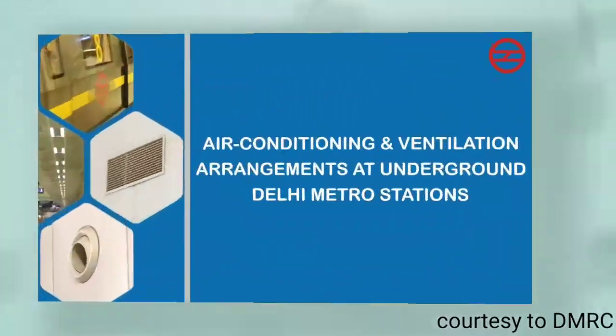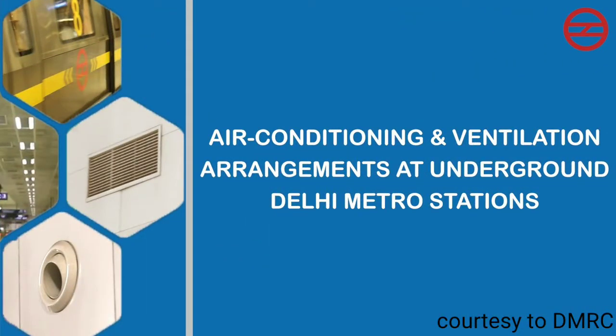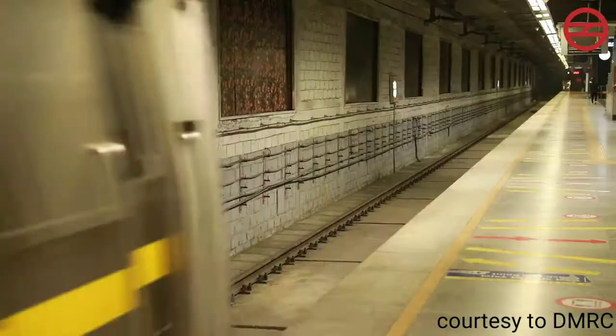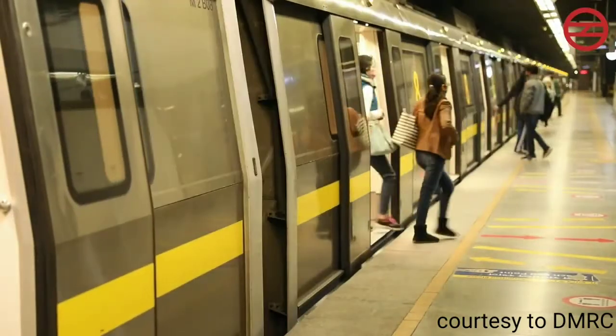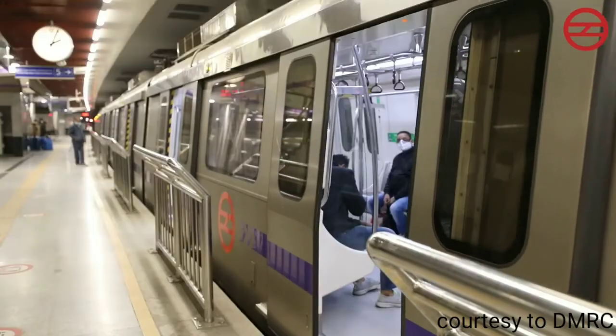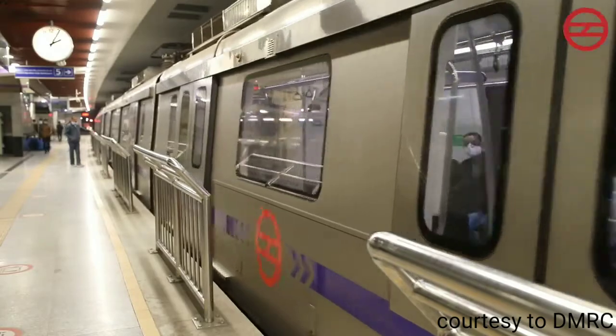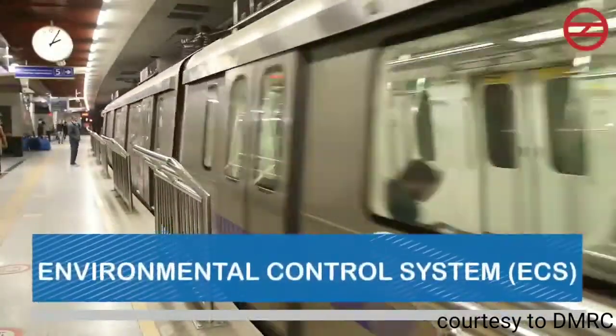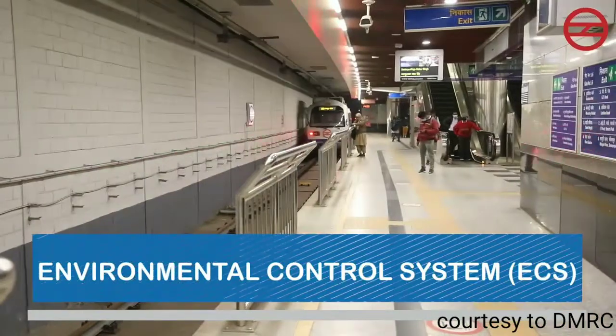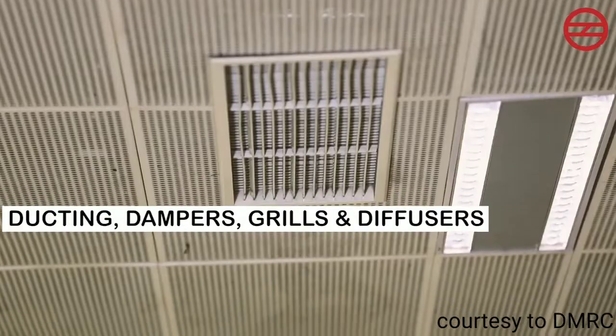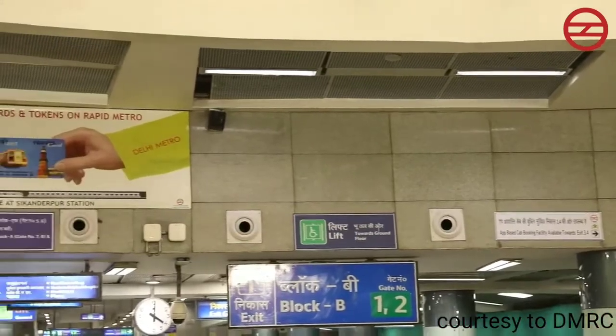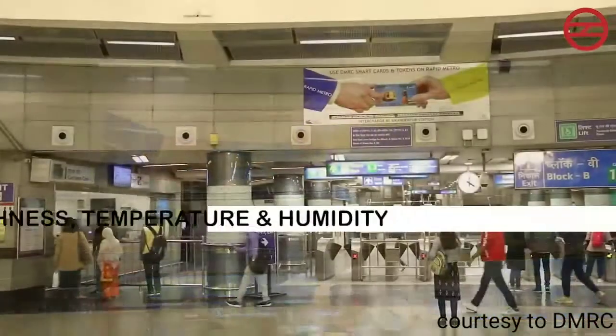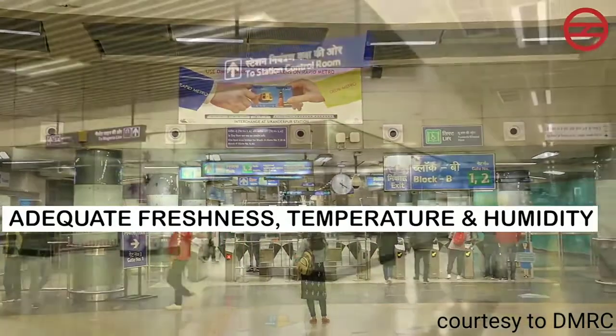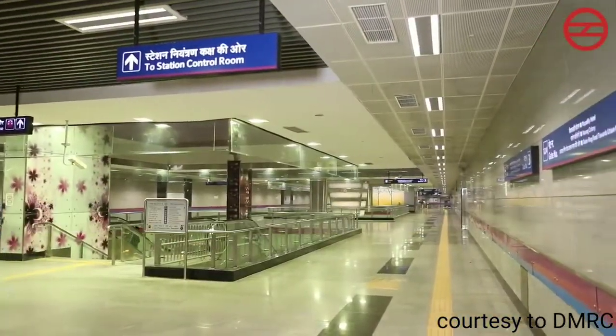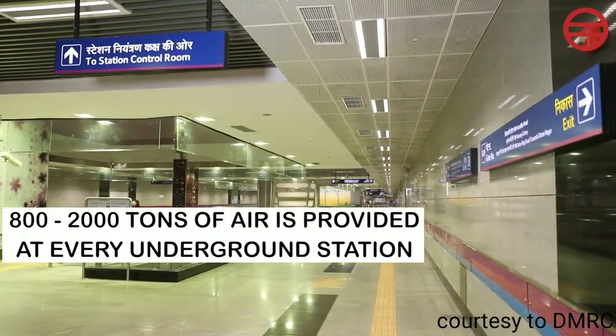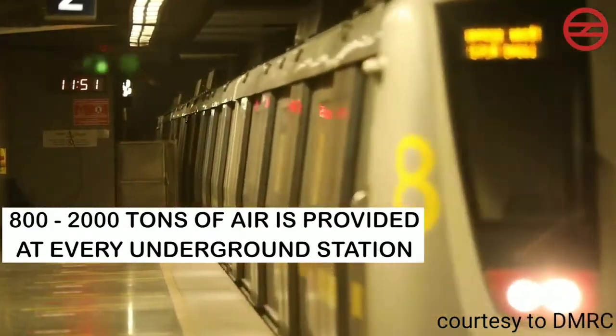Air conditioning and ventilation arrangements at underground Delhi metro stations. For supply of fresh air and removal of body heat, as well as heat generated from electrical equipments in train, a system of air conditioning and ventilation underground is provided, known as Environmental Control System, that is ECS. The ducting, dampers, grills and diffusers, etc. are spread across the entire station to provide fresh, cooled air to maintain adequate freshness, temperature and humidity inside the station. 800 to 2,000 tons of air is provided at every underground station.